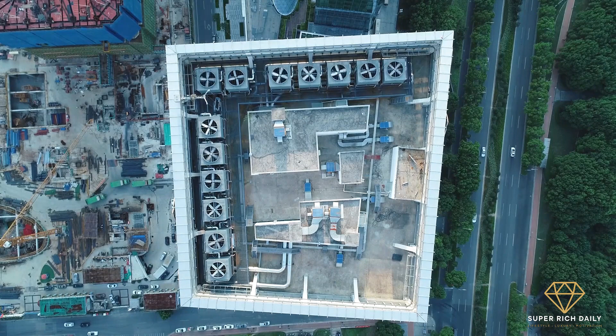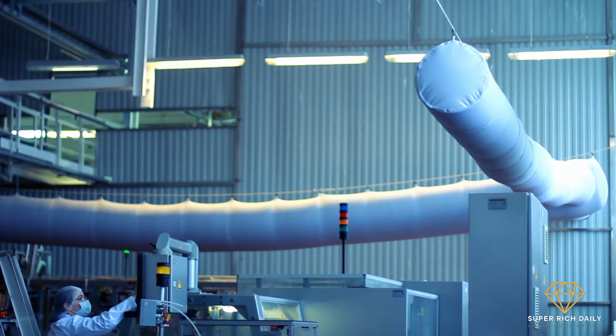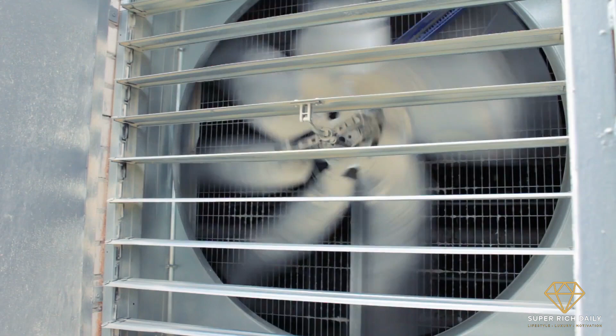Taka Solutions worked with Grundfos to determine the problems around the existing HVAC, heating, ventilation, and air conditioning pumping systems. A Grundfos energy check determined that the buildings were equipped with oversized pumps, inefficient operation, and poor balancing in their constant primary chiller systems. The pumps ran at constant speed. The delta T, the temperature difference between the supply and return chilled water, was only 1 degree Celsius, which in a building's chilling system means extreme inefficiency.